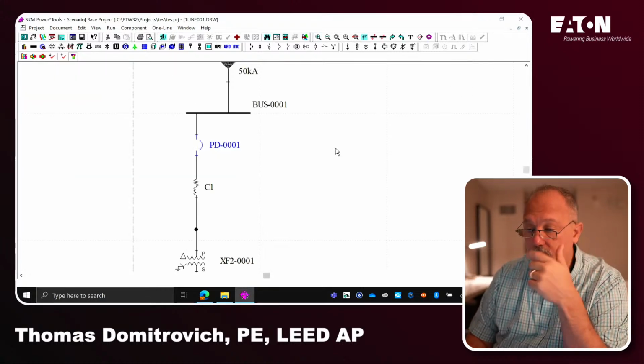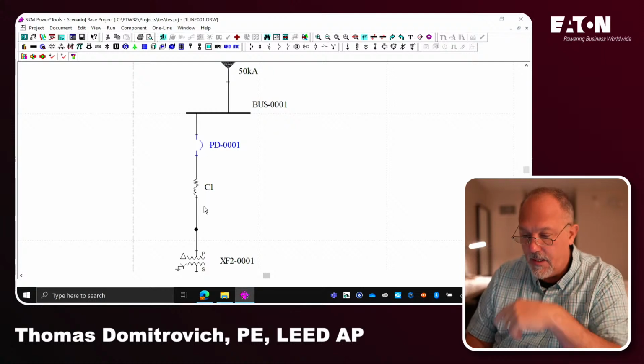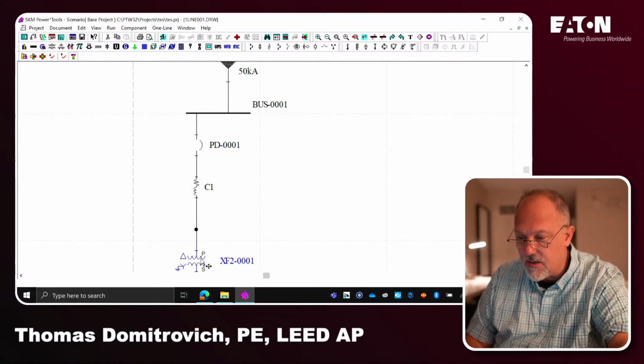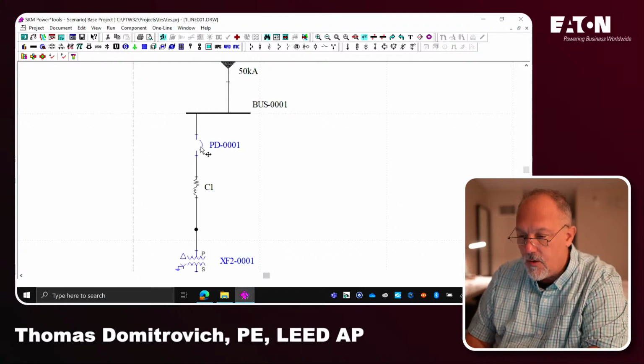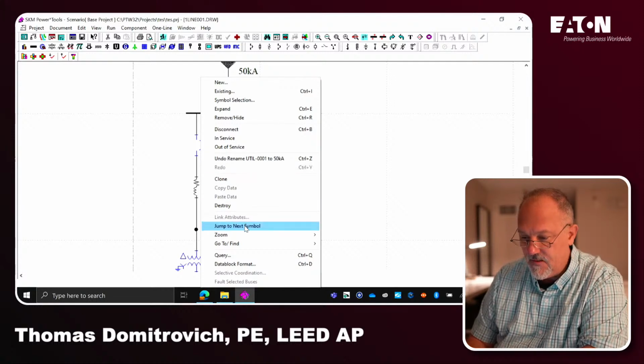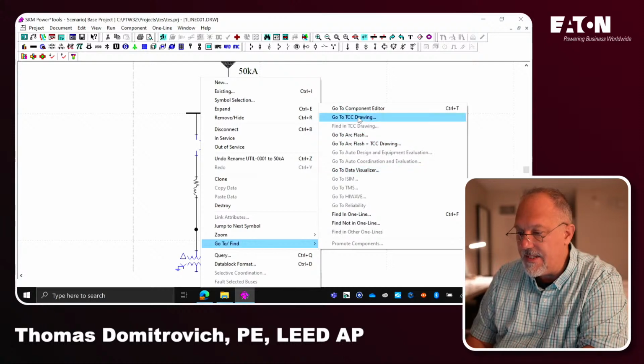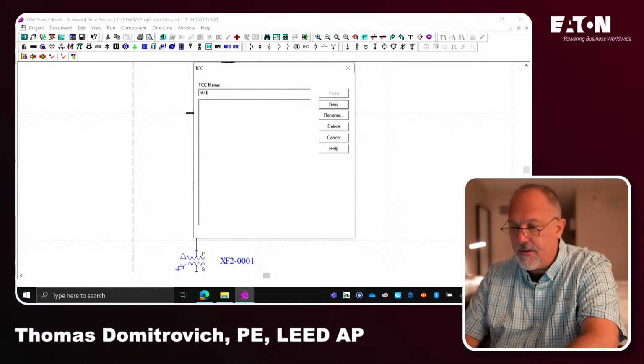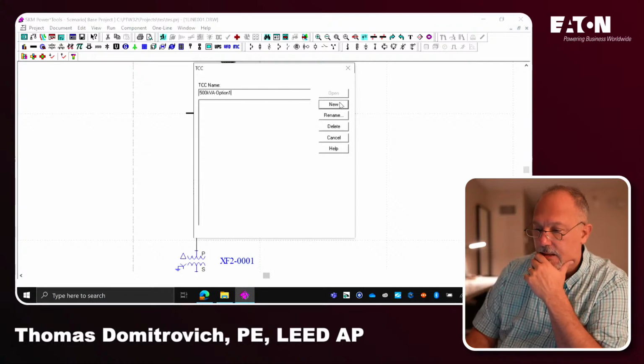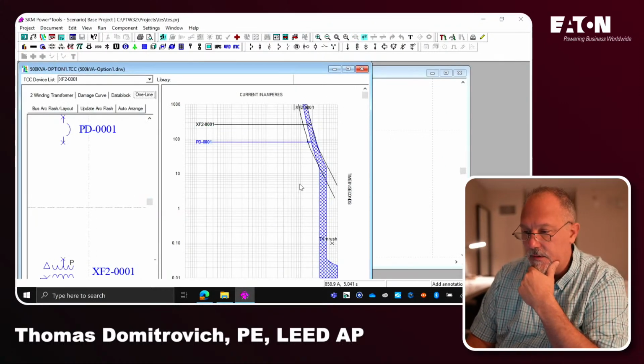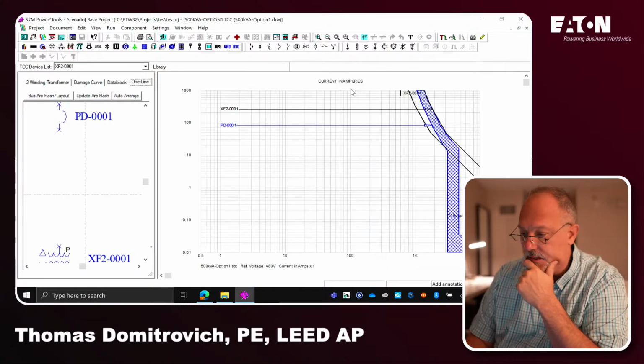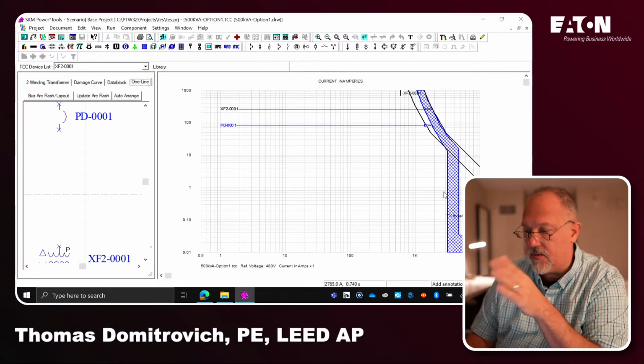Now I'm going to select this breaker, hold the shift key down, and select that transformer, or maybe it's control. Right mouse click, and go to TCC drawing. We're going to call this 500 kVA, option 1, and hit new. There we go. Now you'll notice that everything is way over there to the right.